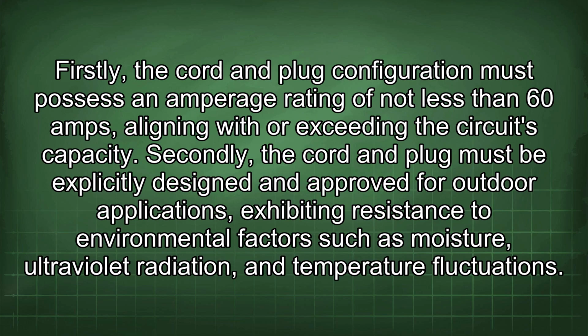Firstly, the cord and plug configuration must possess an amperage rating of not less than 60 amps, aligning with or exceeding the circuit's capacity. Secondly, the cord and plug must be explicitly designed and approved for outdoor applications, exhibiting resistance to environmental factors such as moisture, ultraviolet radiation, and temperature fluctuations.